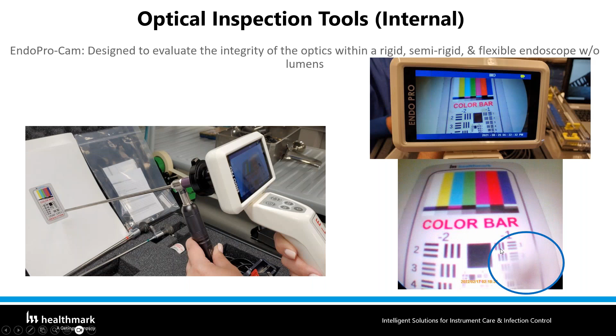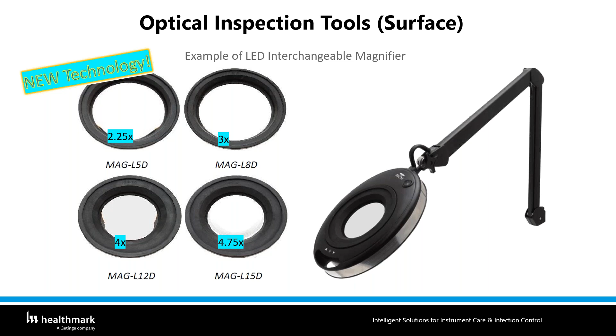Again, here, for example, if you look at that rigid scope under a little more magnification, you see that there's some damage here. And obviously that damage caused the fiber optic to get bent and basically break, so you don't have as many fiber optics going through. So these are all technologies that can help. And this is really a good one, even as a biomed, and you can buy them online as well: a 250 times magnification. It's basically a microscope that you can attach to your laptop or your PC. Again, most of the IFU is talking about some kind of magnification that you can get. For example, with this particular one, you can use various items to do that.